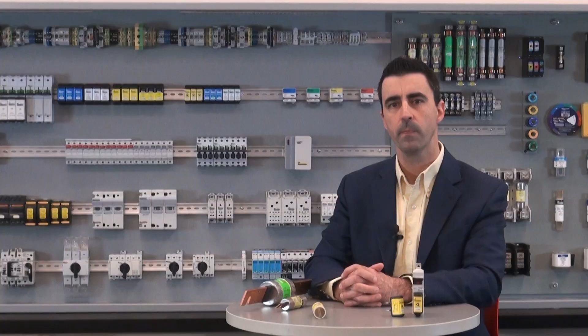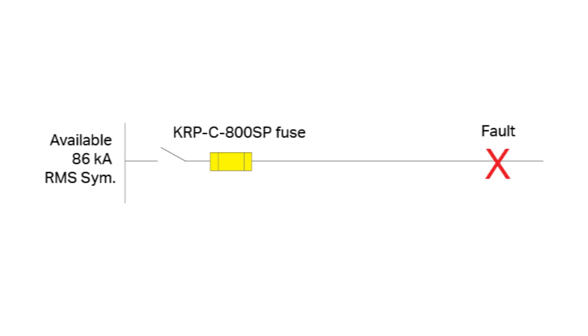Let's go through a real-world example with an 800 amp circuit and an 800 amp KRPC Class L current limiting time delay fuse with 86,000 amp symmetrical fault current available. To determine the peak let-through current, find 86,000 amps on the x-axis and draw a line vertically until the 800 amp fuse curve is intersected. Then follow this horizontally to the instantaneous peak let-through on the y-axis. This value is 49,000 amps. Had a fuse not been used, the peak current would have been 198,000 amps.